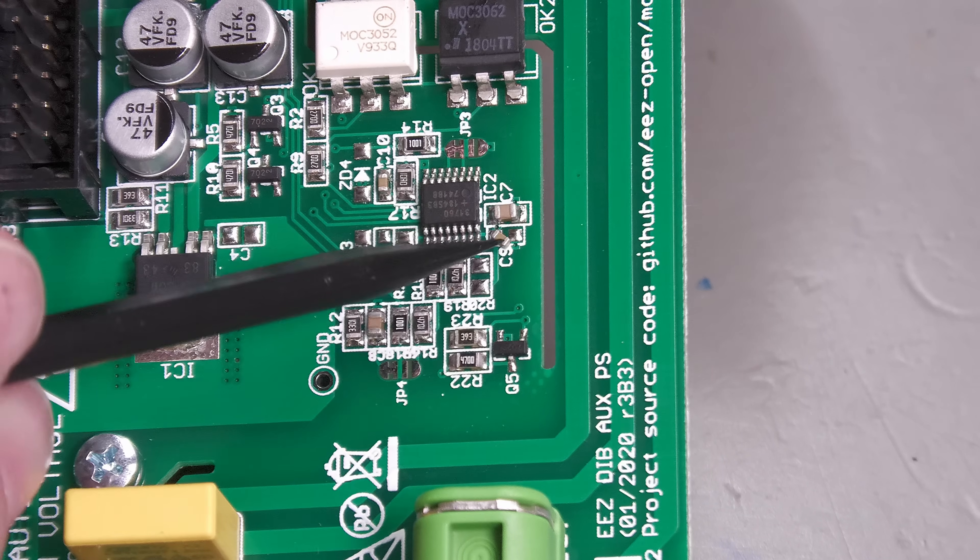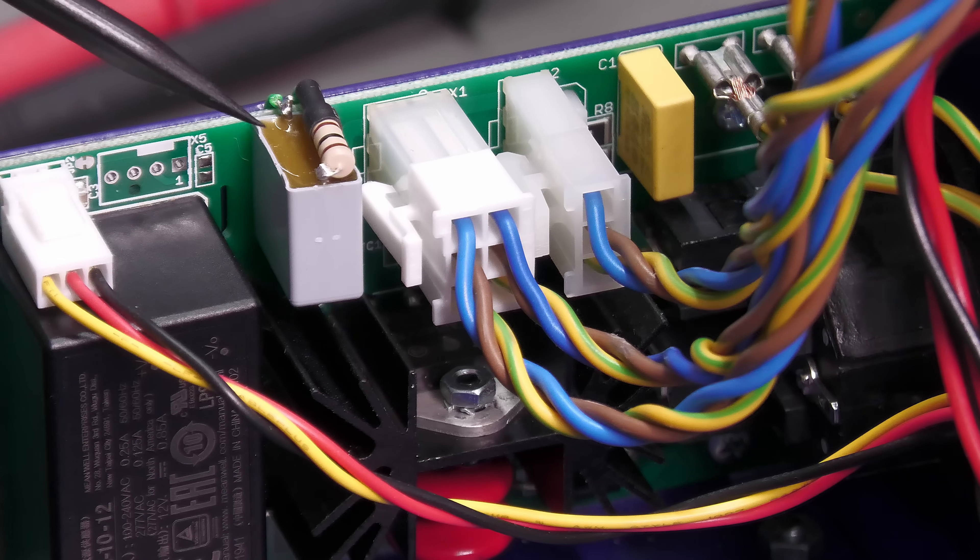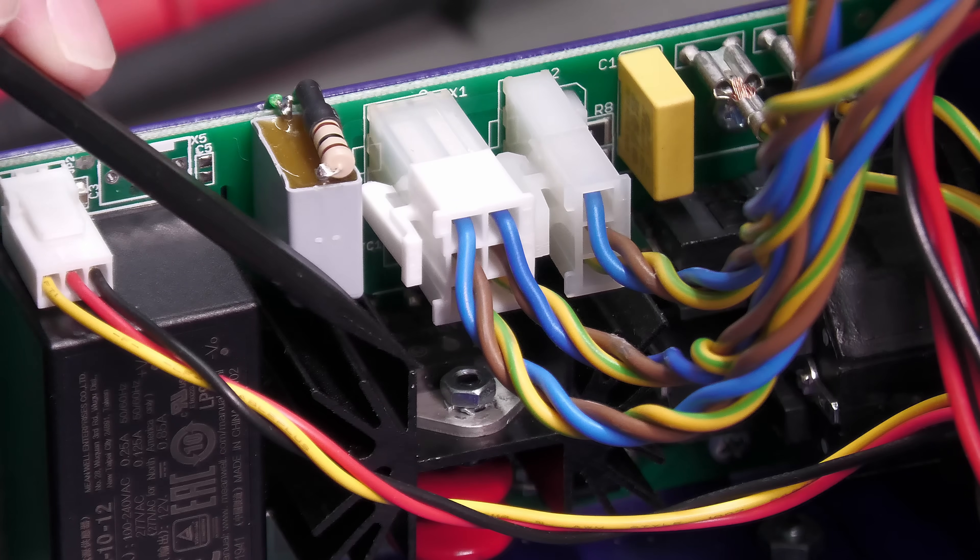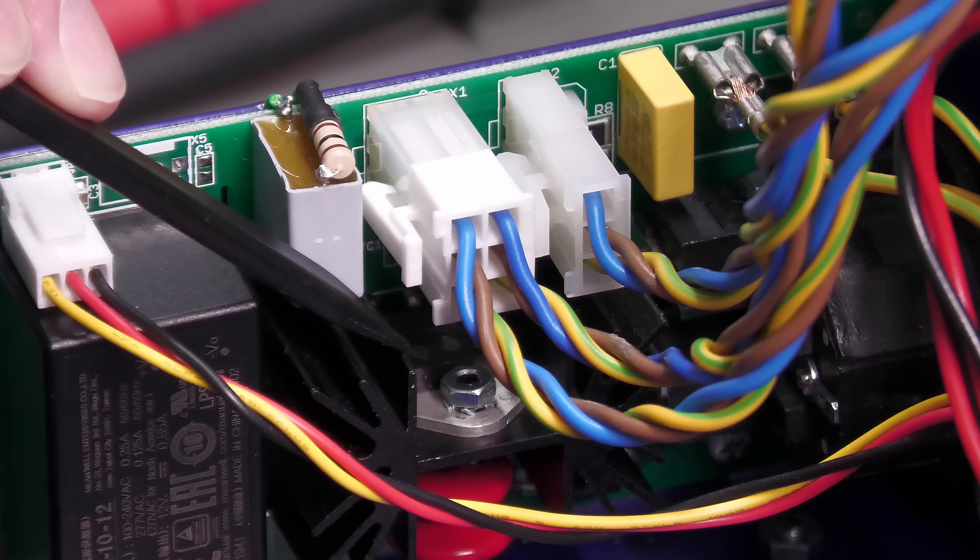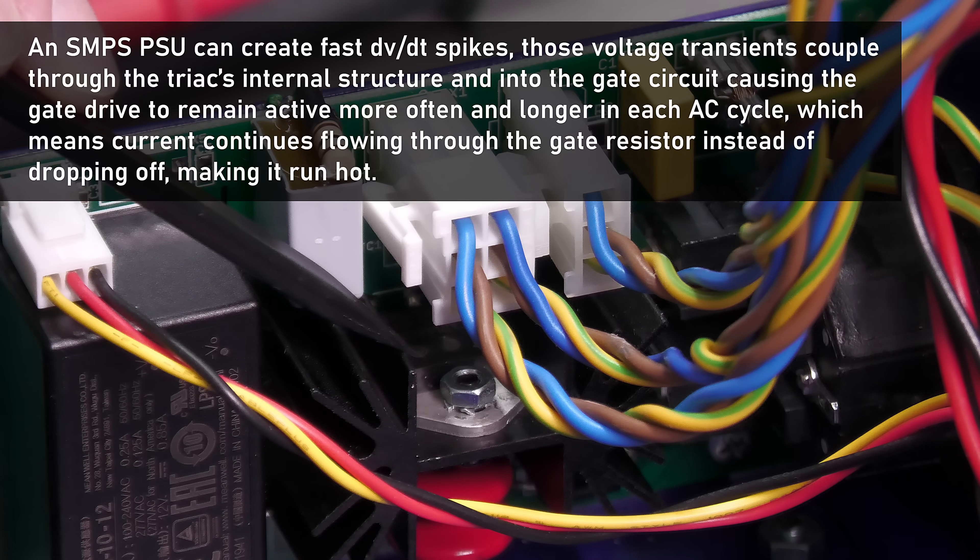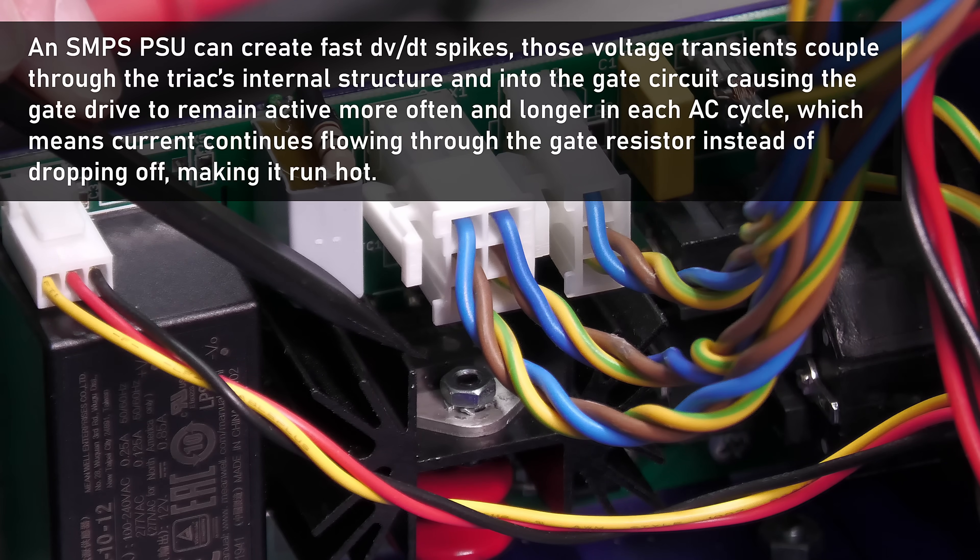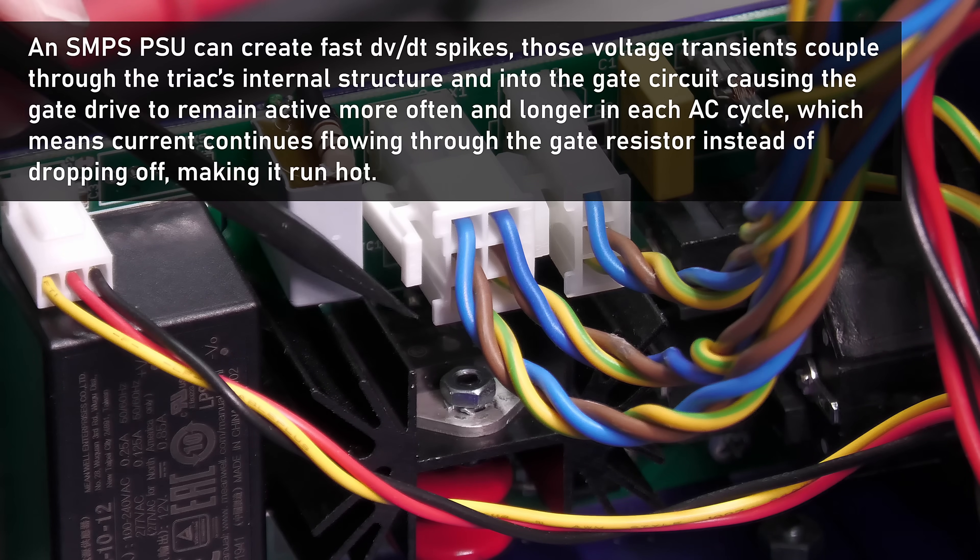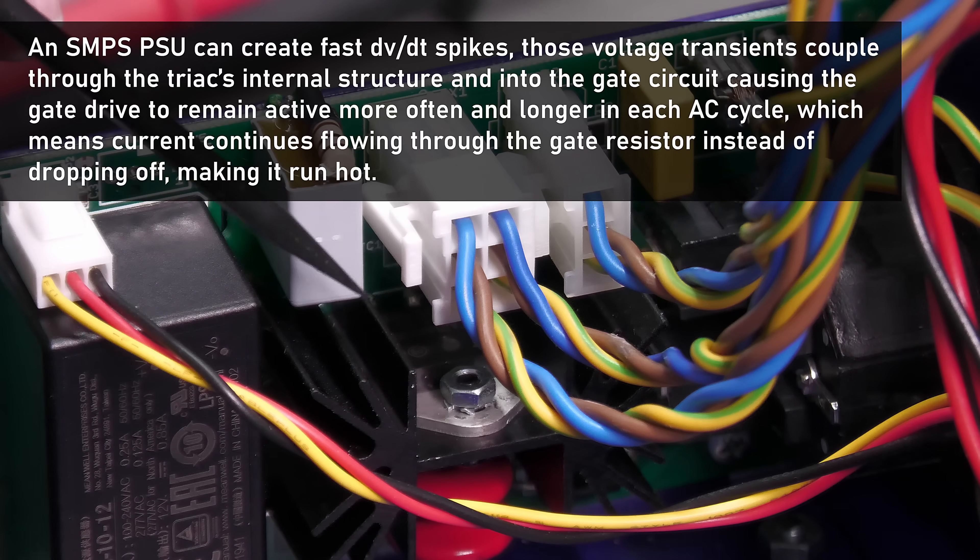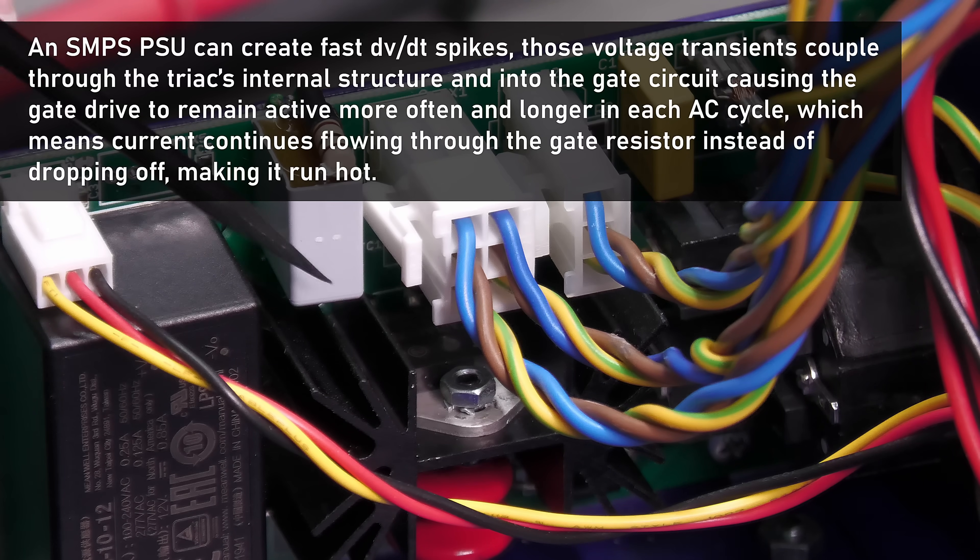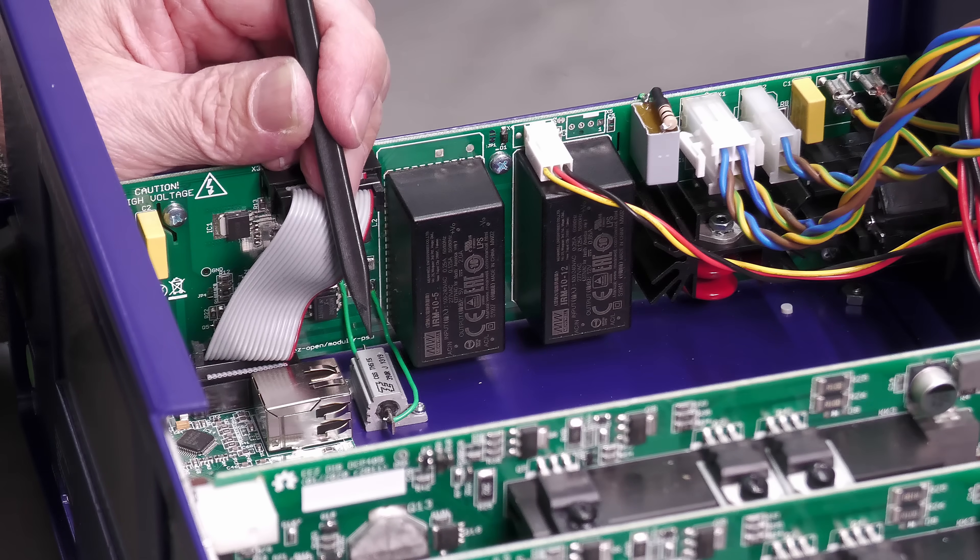I ran another test. I fitted another snubber across the A1 and A2 terminals of the triac, because I'm thinking there's perhaps quite a lot of dV/dt noise in the system generated by the SMPS LRS power supplies, and that's what's causing the R4 resistor to heat up. When I disconnect the LRS power supplies with these connectors, the temperature of the resistor drops. However, this snubber didn't make any difference.